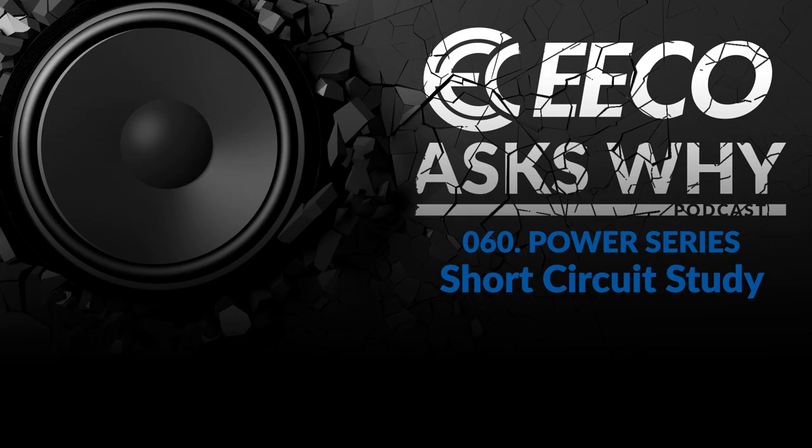So we're not really talking here about arc flash, but arc flash is probably one of the most important phenomena that we've looked at in modern times. And the short circuit, or the device's capability to clear the fault, is paramount to arc flash. If I can't depend on the breaker to trip and clear the fault at a certain time, then the arc flash study kind of goes out the door. That's kind of why we do arc flash and short circuit together. Not only do we do an arc flash incident energy calculation to determine the hazard risk of arc flash, but we also look at the components to make sure that they will properly operate.